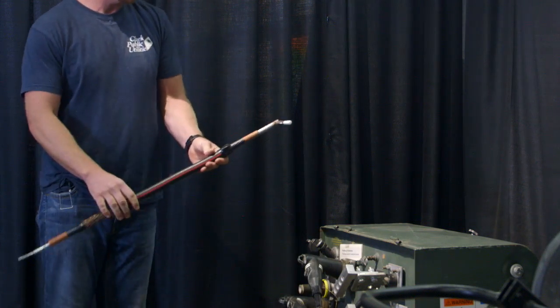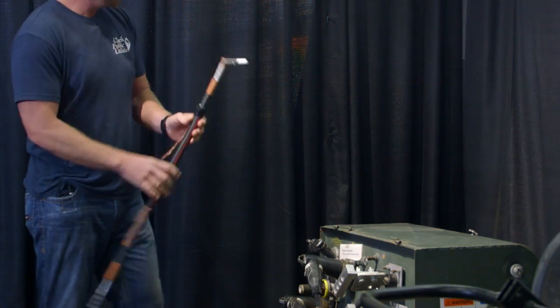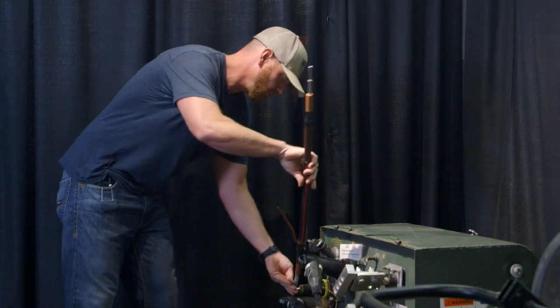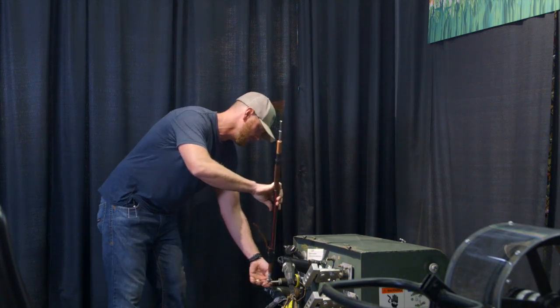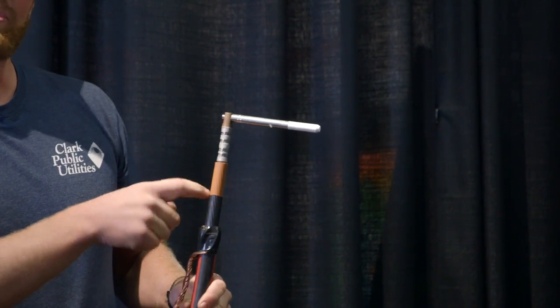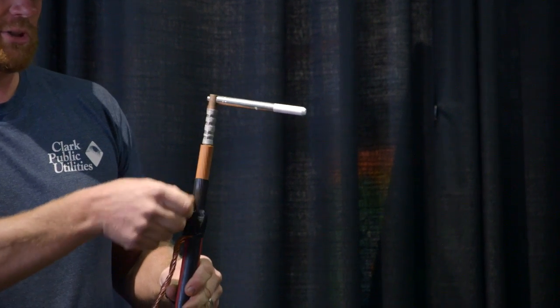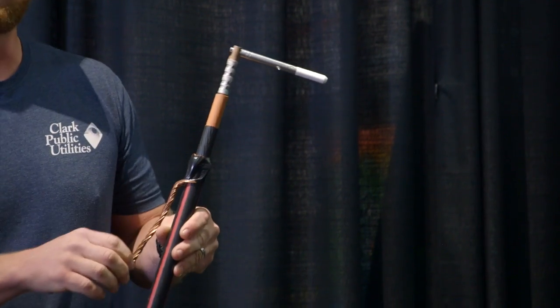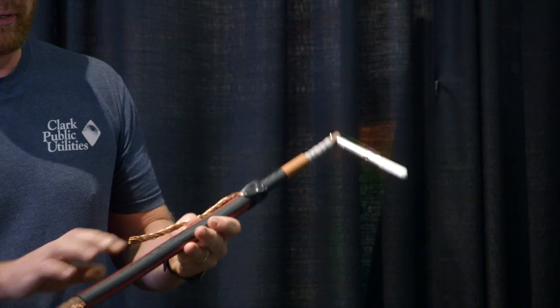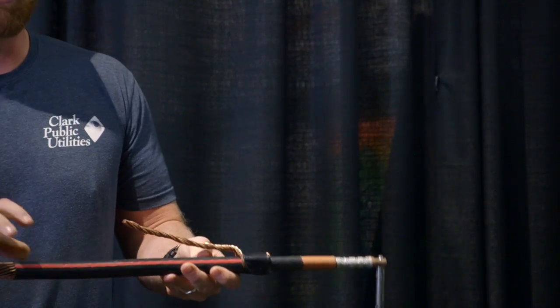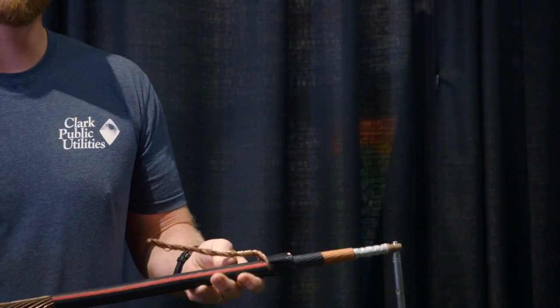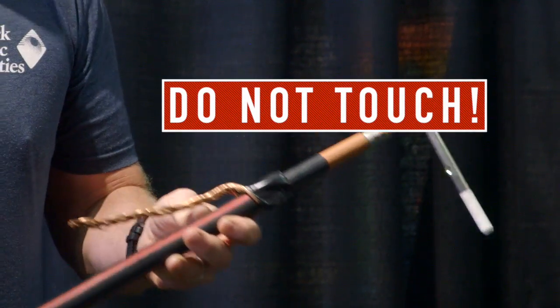Here's kind of how it looks inside of that. We've got a probe that just inserts into the transformer - that makes your electrical connection. Here's some insulation wrapped around the aluminum conductor, some semicon, and then a copper concentric that we use as our neutral. It also has a red and black jacket on it that denotes this is a power line when you find it in the ground. If you find this, please don't touch it.